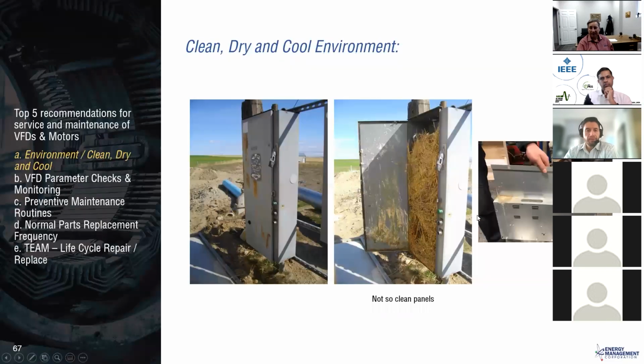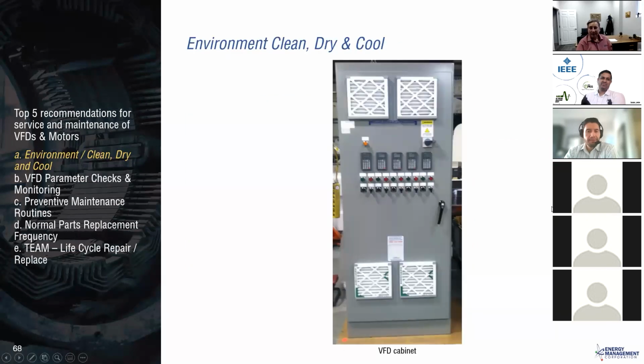And this last area of the service, this doesn't go real well as far as our clean, dry, and cool. This one over here, the customer asked why this drive failed. Well, we found all kinds of rat urine and droppings inside the drive, on the circuit boards primarily. So that's pretty obvious. This is interesting when you think about it from an arc flash standpoint.